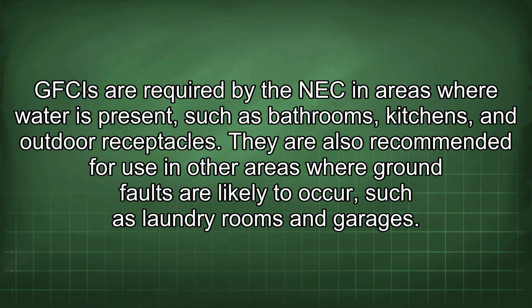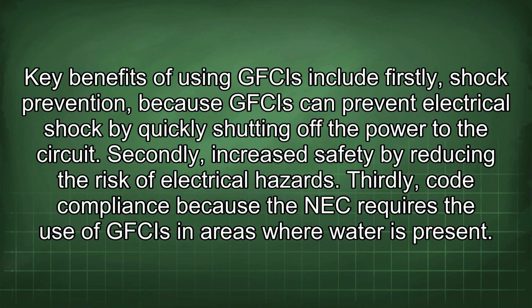They are also recommended for use in other areas where ground faults are likely to occur, such as laundry rooms and garages. Key benefits of using GFCIs include, firstly, shock prevention, because GFCIs can prevent electrical shock by quickly shutting off the power to the circuit. Secondly, increased safety by reducing the risk of electrical hazard. Thirdly, code compliance, because the NEC requires the use of GFCIs in areas where water is present.